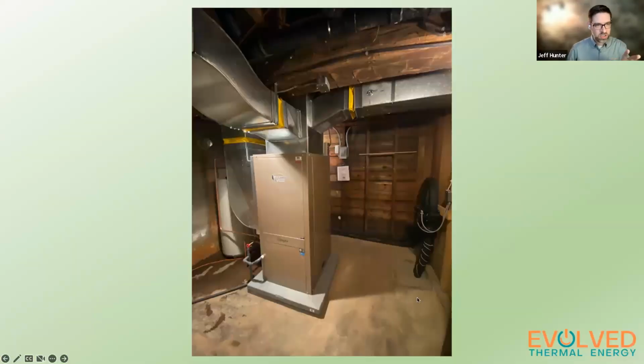Let's take a look at the installation in your basement. Most houses in Ontario use some kind of forced air system, so this heat pump has to be retrofitted into that ductwork system. Heat pumps move more air than a common fossil fuel furnace, so part of the considerations for the installer is how to adapt the ductwork system. You can see a very large return air drop here, and a larger plenum adapted to the existing ductwork.